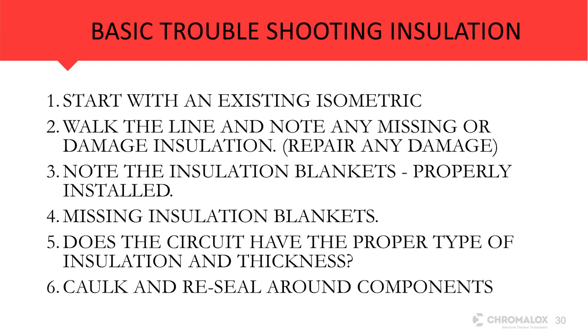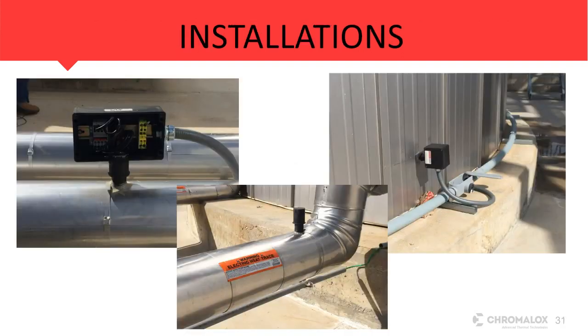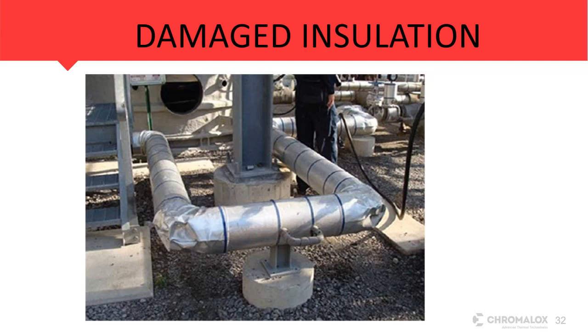If we look at clean insulation on projects that have been installed, you can see the jacket in here is nice and clean and smooth. It's caulked around the power boxes and my end seals. They're caulked up really nice and neat. But when you really go walk down a job, this is what we kind of see. We see busted corners on the insulation. If you look over to the right next to the gentleman, you'll see there are insulation blankets missing on that valve.